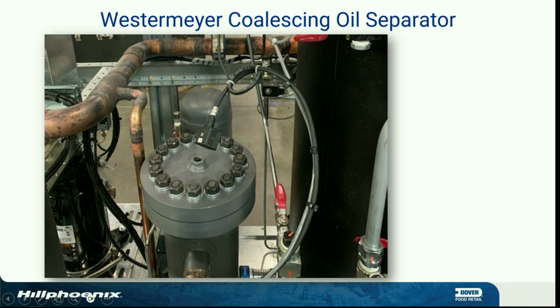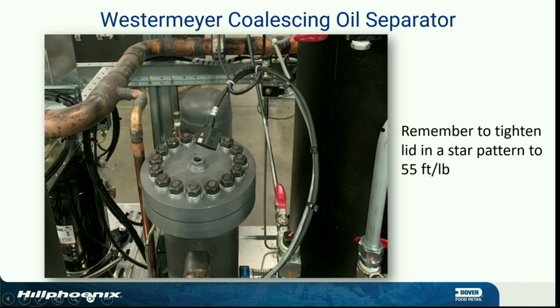And then go to 55. If you still have a leak at 55, what are you going to do? Tighten it a little more. Get it sealed. Get it working. It's actually a Westermeyer spec: 55 foot-pounds, if it leaks, tighten more. Not spec, it's a suggestion. Remember to tighten the lid in a star pattern to 55 foot-pounds.